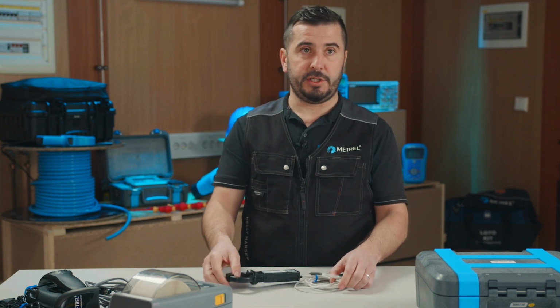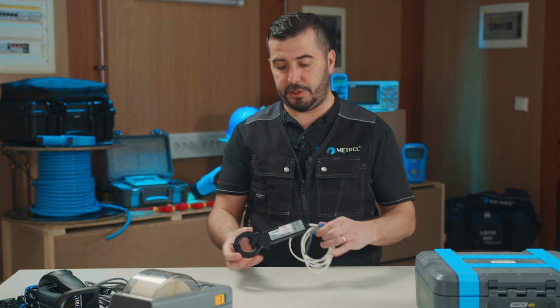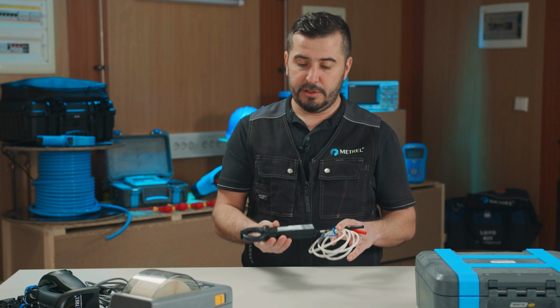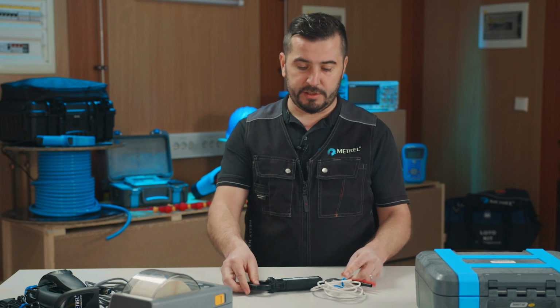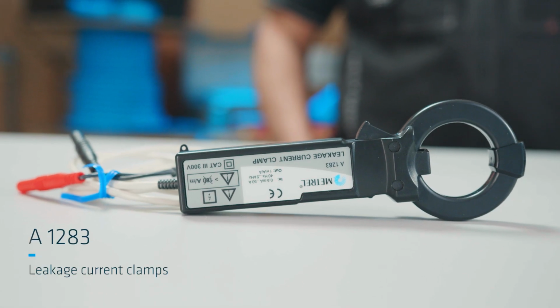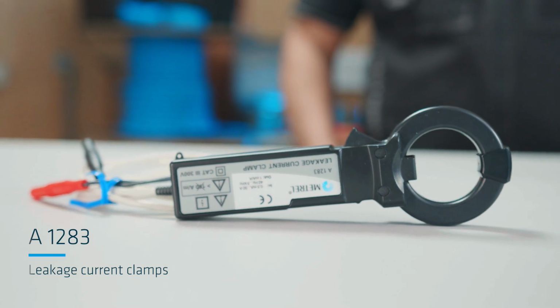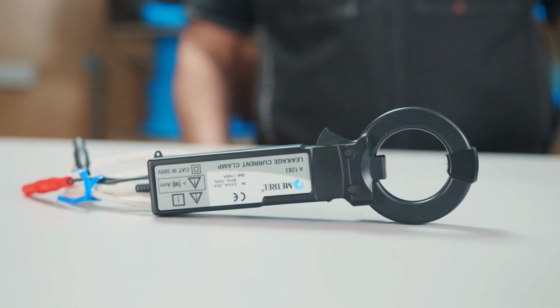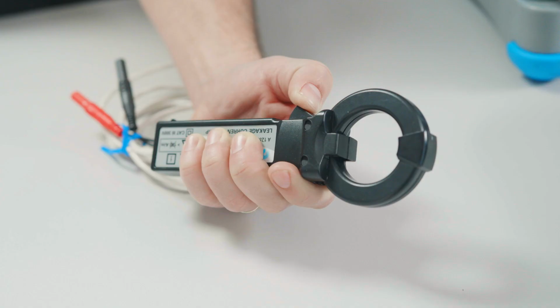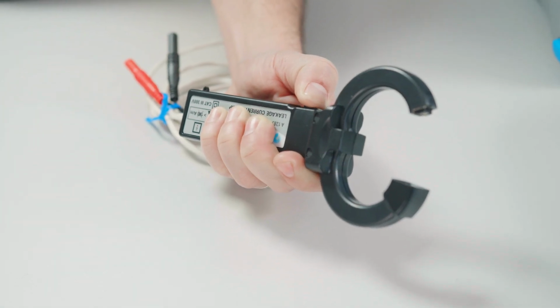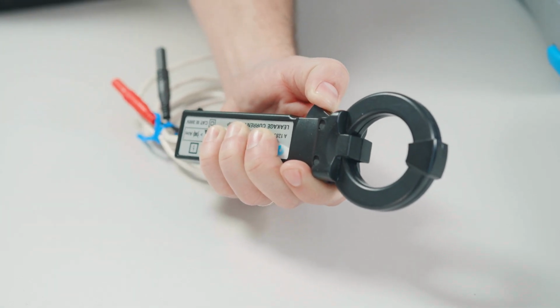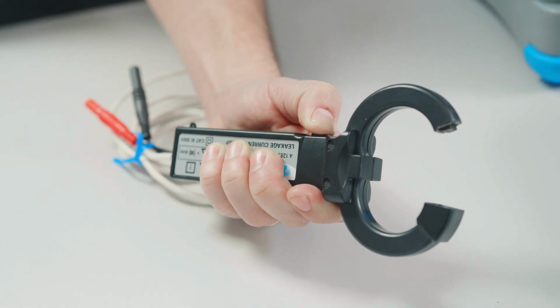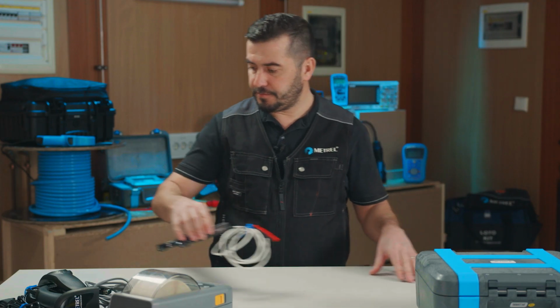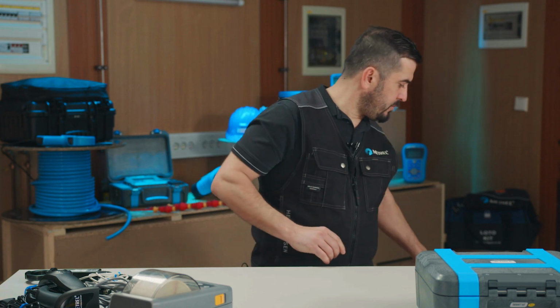Sometime during the presentation of our instrument, I also mentioned that we have the possibility to connect a very precise leakage current clamp to the instrument. So these are the clamps. There are two probes which we connect from the left side of the instrument, and we can then measure leakage currents of our appliances.